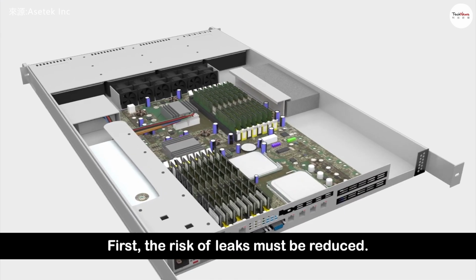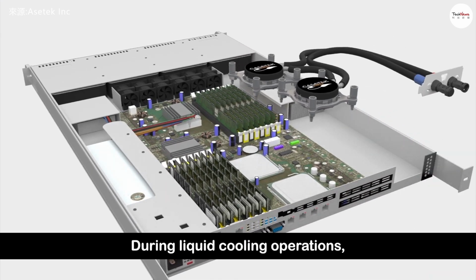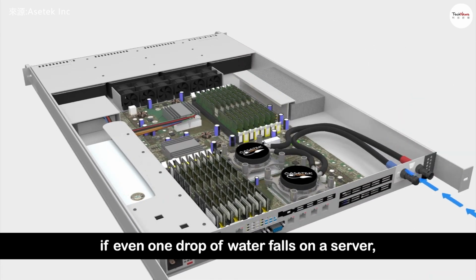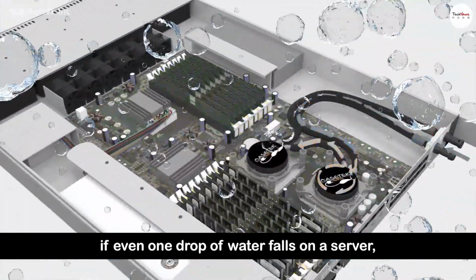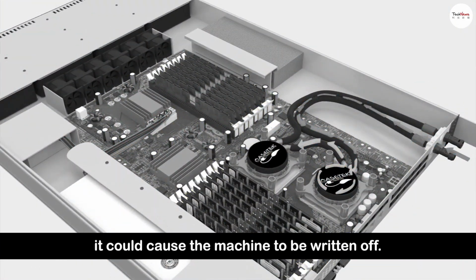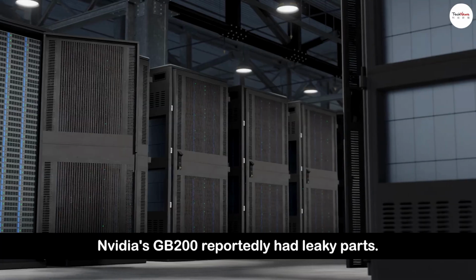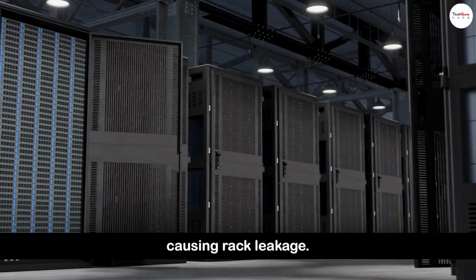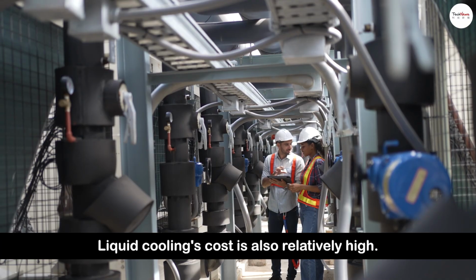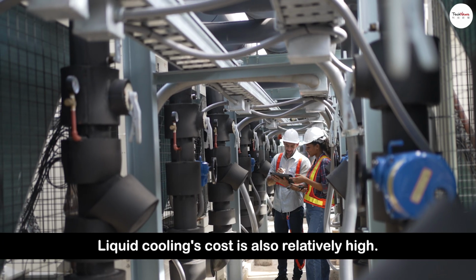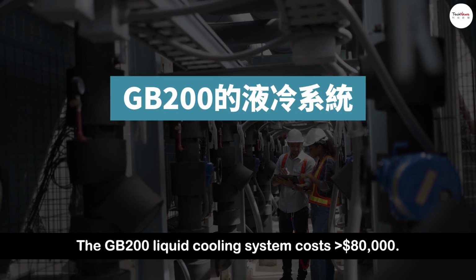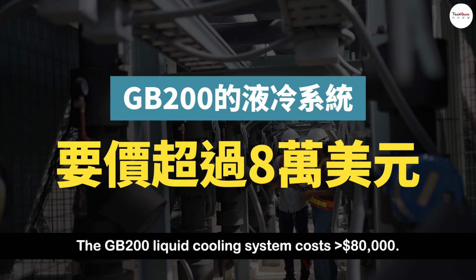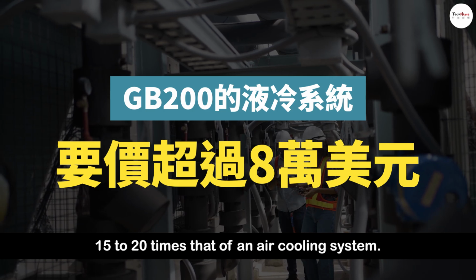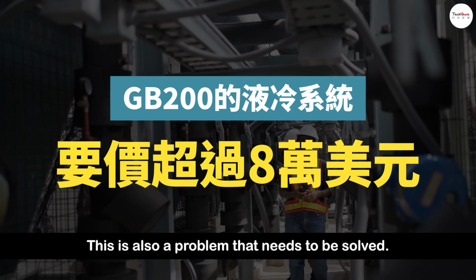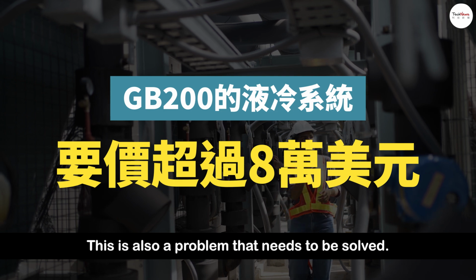First, the risk of leaks must be reduced. During liquid cooling operations, if even one drop of water falls on a server, it could cause the machine to be written off. Nvidia's GB200 reportedly had leaky parts, causing rack leakage. Liquid cooling's cost is also relatively high. The GB200 liquid cooling system costs over $80,000, 15 to 20 times that of an air cooling system. This is also a problem that needs to be solved.